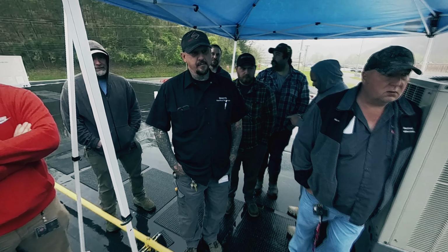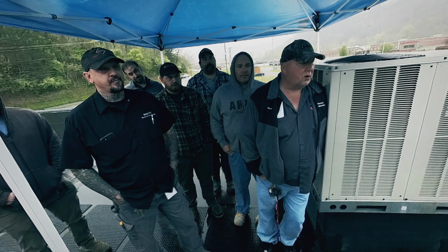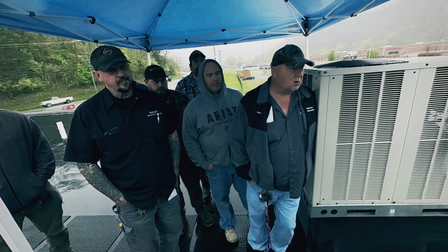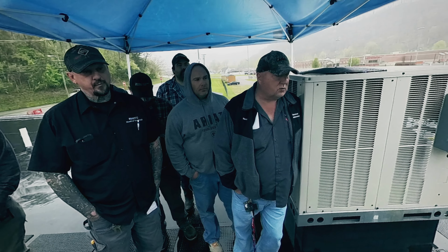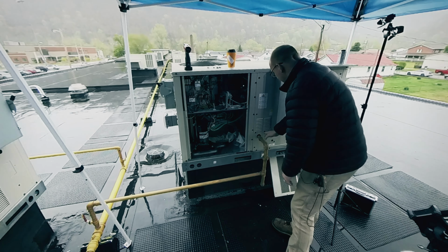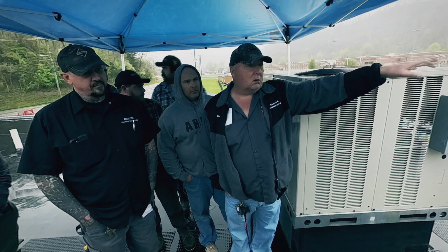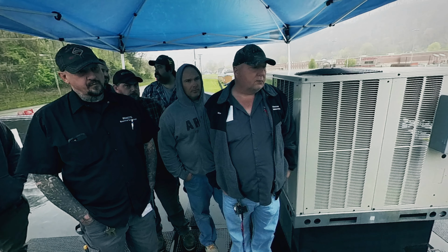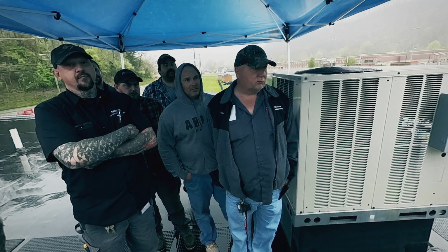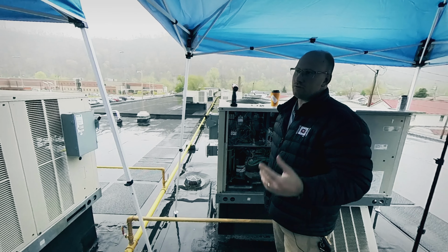Is it direct drive or belt drive? No, it's direct drive. It's ECM direct drive. Is there a combustion tube access, a door? No, so you've got to take this whole door off. Your heat chambers sit right here. They go this way, and that's like on the other side. Now, there's an access on the side, on the other side there. It's about a 12 by 12. You can take the screws out to check your tubes, yes.